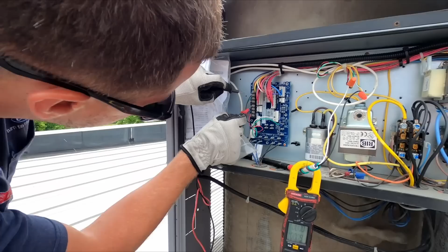Oh, SpaghettiOs. Shut the power off, test capacitor. Well, this is 3-phase, so no, that capacitor is for the condenser fan motor. I don't have a contactor pulled in, so the condenser fan motor is not going to run.